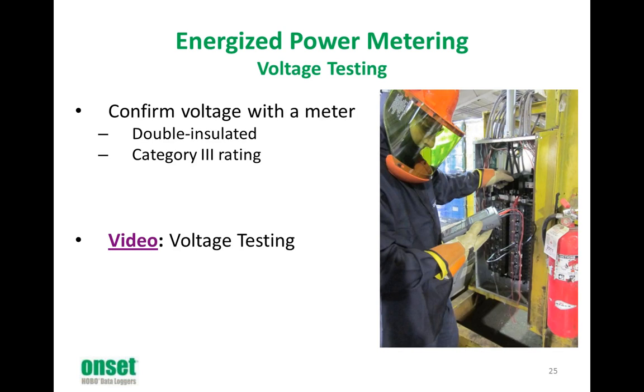So once we gain access, it's still important to confirm the voltage with a meter. Make sure that voltage meter is double insulated and category 3 rated. So those $10 multimeters don't always work well in these situations. You want to make sure you have a heavy-duty meter that's rated for this voltage. Now we'll watch a short video on voltage testing.